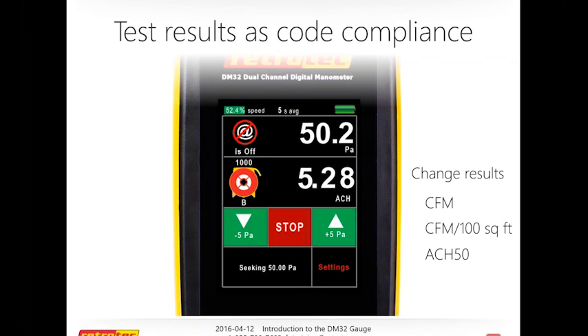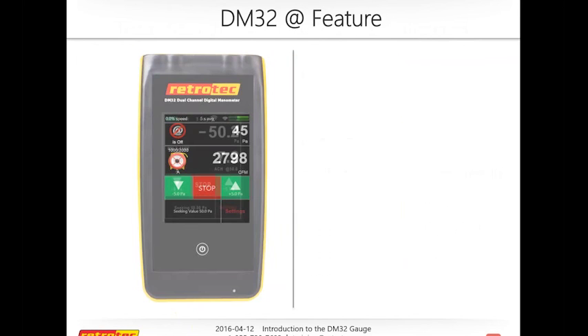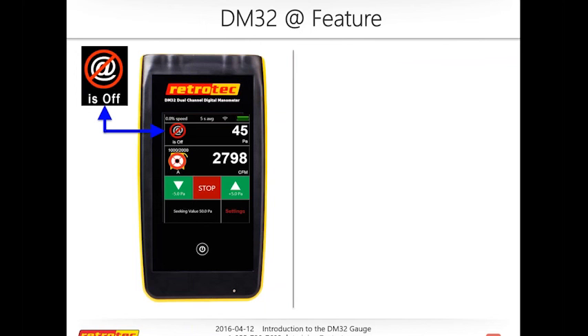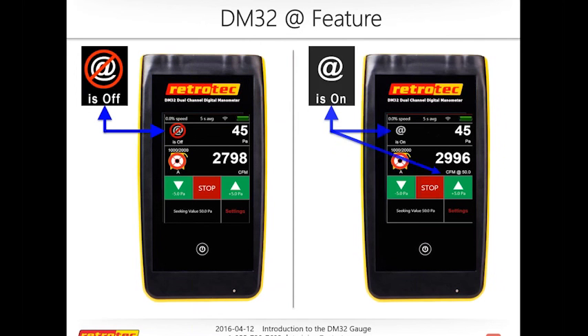So another feature, and if any more questions, I am getting to your firmware, so thank you so much again for being patient. Another great feature is this: you have what we call an "at" button, and it can extrapolate what the pressure would be if it was at the pressure you set it to. So if I'm seeking a pressure of 50 and I can only get up to 45, I click here and this is telling me what that pressure is at 45. But then I click here and it says, well, what would it be if you're at 50? And then you can see this gives me a different result.